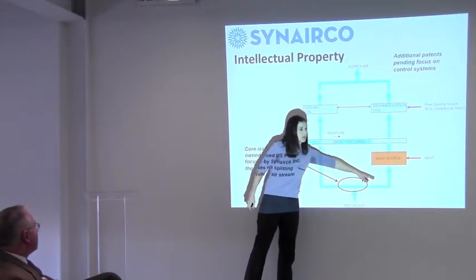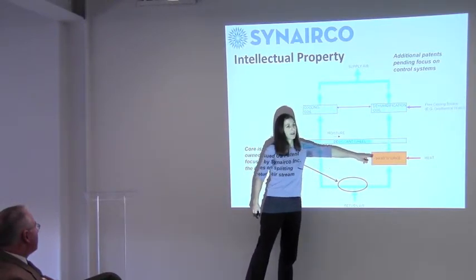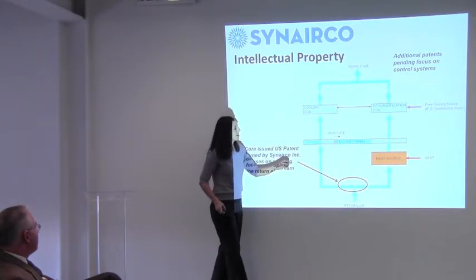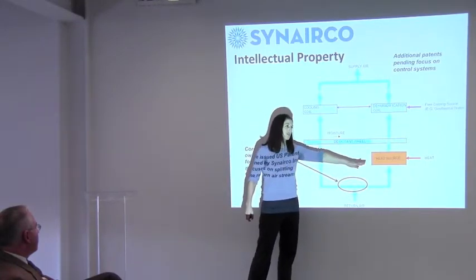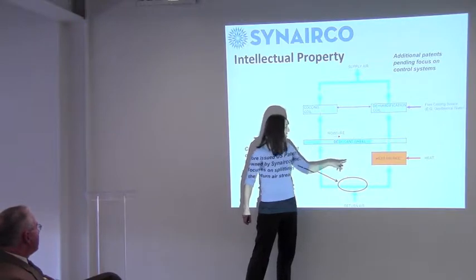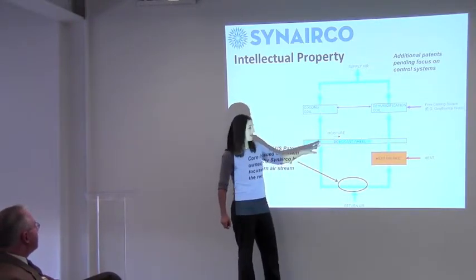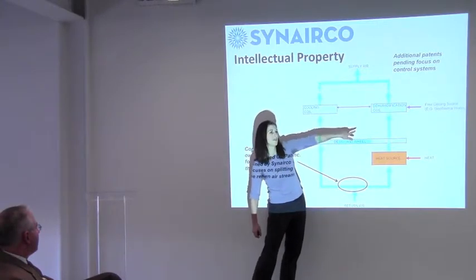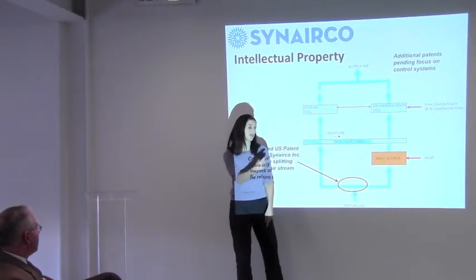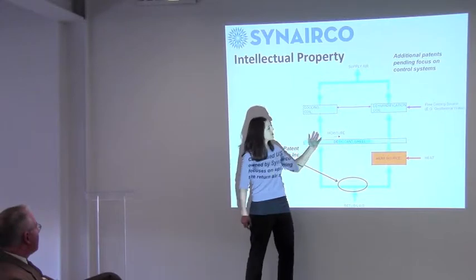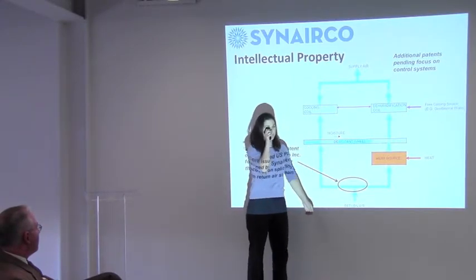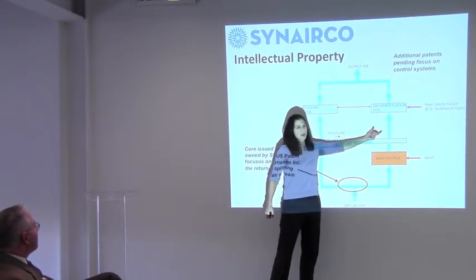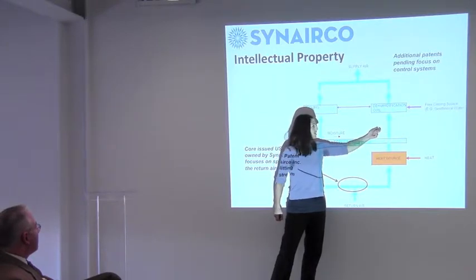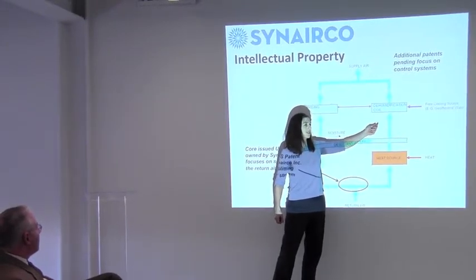This tiny airstream, we heat up, okay? You can use any source of heat, and it's a mild source, about 160 degrees. Then we pass both airstreams through a desiccant wheel. In this schematic they're shown going in the same direction, but in a desiccant wheel they have to go counterflow. We transfer all the moisture into that heated airstream. Now we've got this small, heated, and really saturated airstream whose dew point has changed.